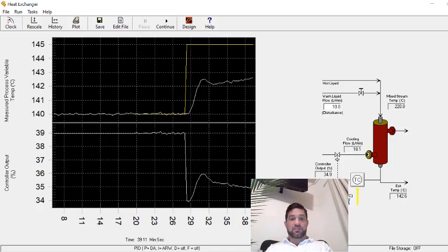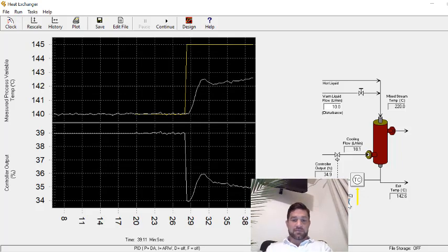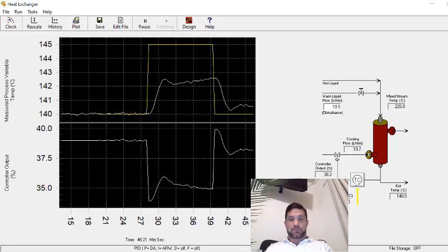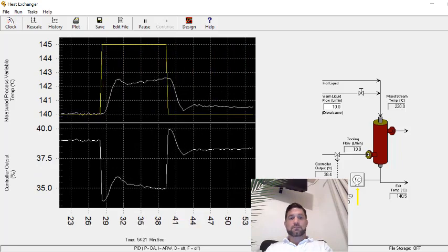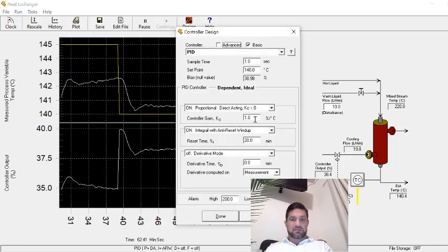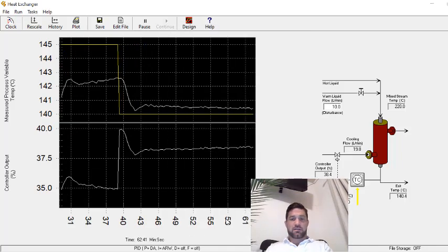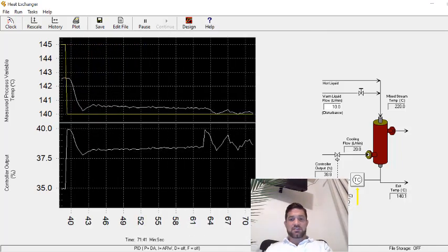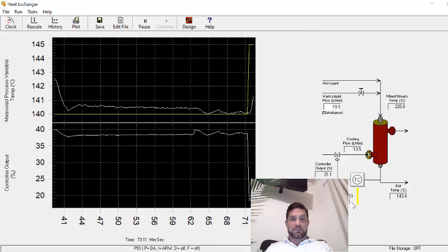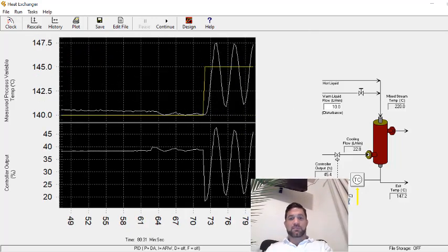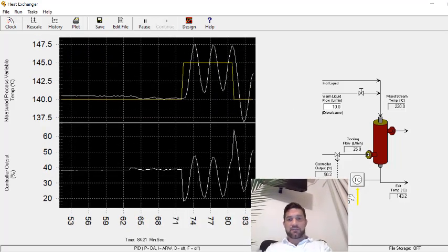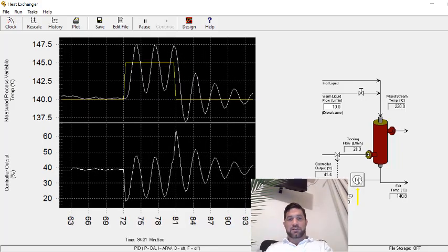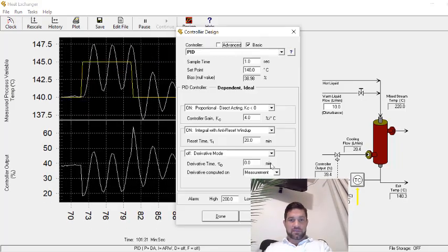I didn't get any overshoot, but also I don't have 16% first peak to valley relative to the step change. So I'm going to step this back down to 140. Now let's change this to a gain of four and do a step change to 145. Oh yeah, that's way too much. Step this back down to 140.